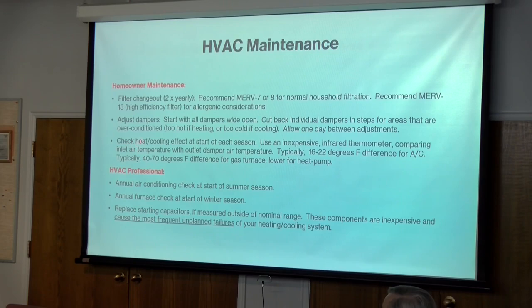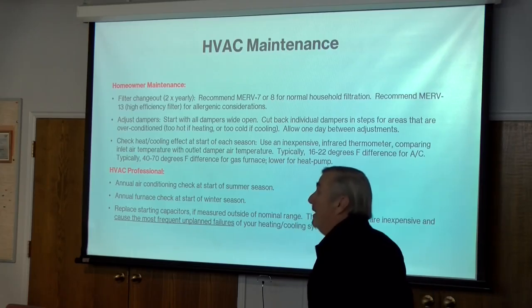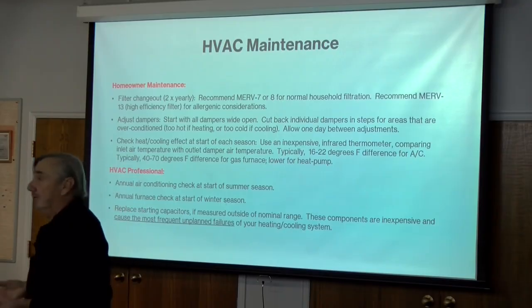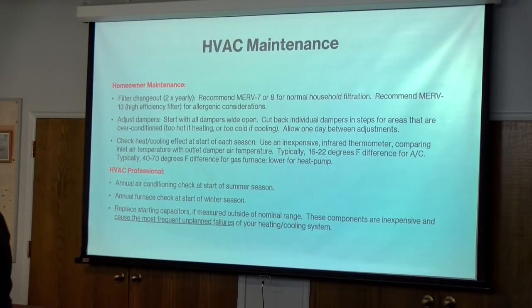The other thing I recommend doing is checking your heating and cooling effect at the start of each season. You can do that with a fairly inexpensive tool, an infrared thermometer, by measuring the temperature difference your system creates when it's operating. Typically an air conditioning system runs with a temperature difference between the inlet and the outlet of about 20 degrees. So when it's operating, you ought to be able to measure that temperature difference at around 20 degrees.